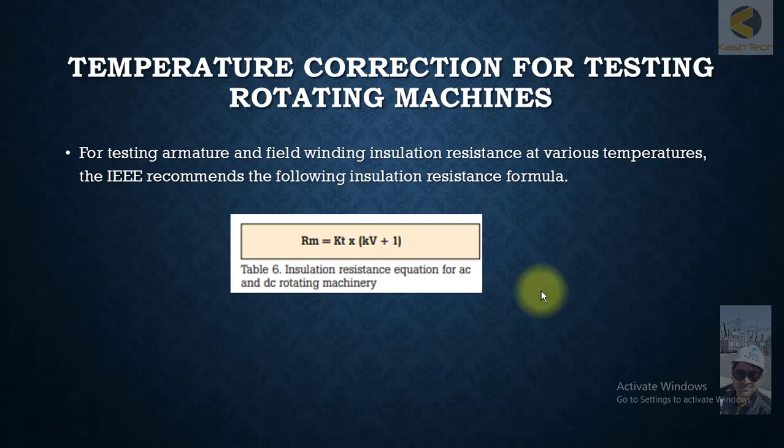You can select other base values, and then we can compare. All the manufacturers are providing the coefficient or correction factor by which you can find out the real resistance. For testing armature and field winding insulation resistance at various temperatures, the IEEE recommends the following insulation resistance formula.